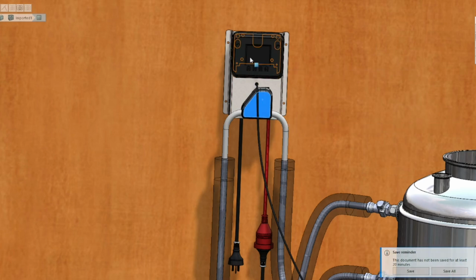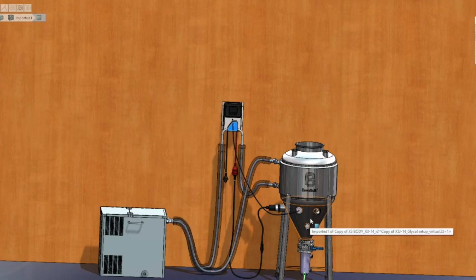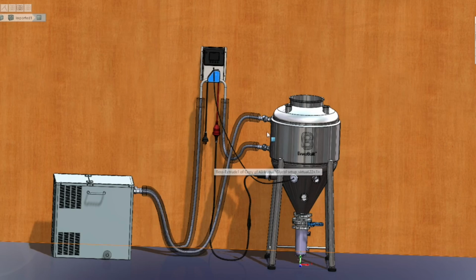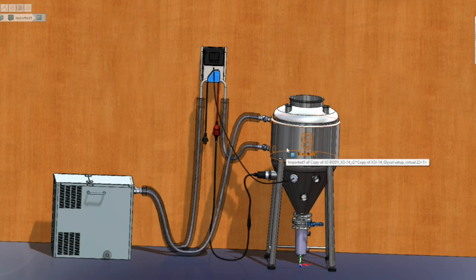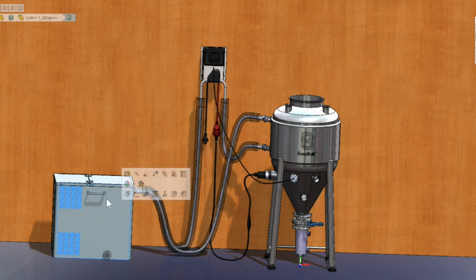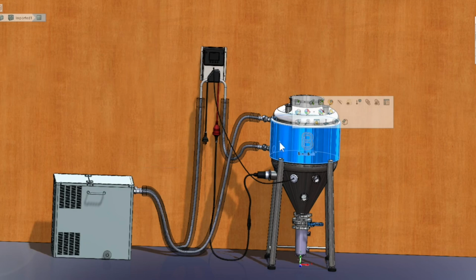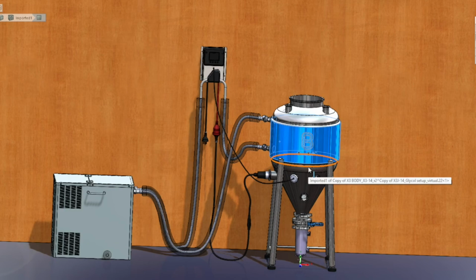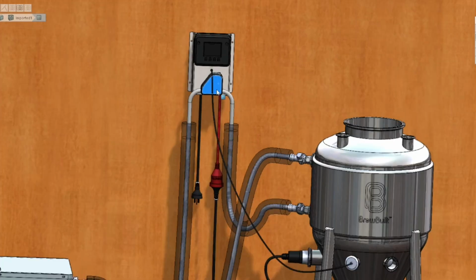What we can do is use a PID function in the glycol controller to reduce flow to the tank, and that's quite handy in this instance. There are a lot of cases where PID is overused in home brewing and not really necessary, but with glycol in particular, especially at around -1 degree, if you're pumping that through a jacket of several liters, you can easily overshoot and overcool the jacket or fermenter, even for just a few seconds. So for glycol cooling a 20, 30 or 50 liter fermenter, a PID, especially the proportional coefficient, is really handy to make sure you don't overshoot the set temperature.